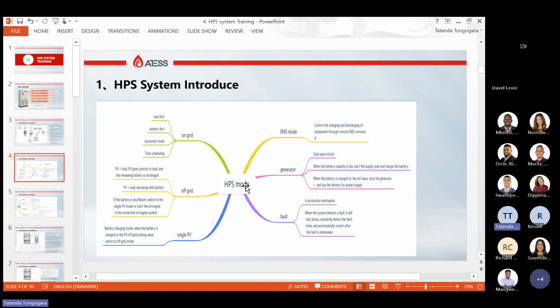HPS system, the HPS mode, we have on-grid mode, off-grid mode, and single PV mode. You can also use it in EMS mode. So in on-grid mode, you can select load first, battery first, economic mode, and time scheduling. So on time scheduling, let's say between 5 maybe to 9 p.m., the tariffs are very high. You can set your system not to use any grid at this time so that you can save on your tokens. And then economic mode is the same thing.